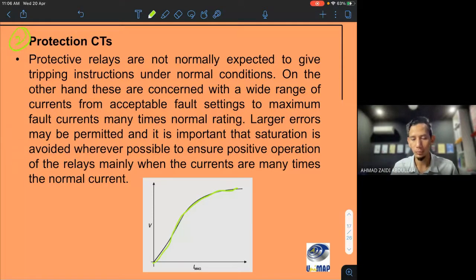Protection level, let's say you buy a CT for the CT that controls the ELR. So the ELR functions based on whatever value is transmitted from the CT. This CT may be a ZCT or whatever current transformer. So let's say 100 amp comes in, going through the CT, and then the CT will convert it to just 5 amp or 10 amp. From this value it will transmit to the ELR, and the ELR will send the signal to the breaker to switch on or switch off. Normally they place a breaker here, either ACB or MCCB and so on. So it depends on this ELR, the ELR will send the signal.